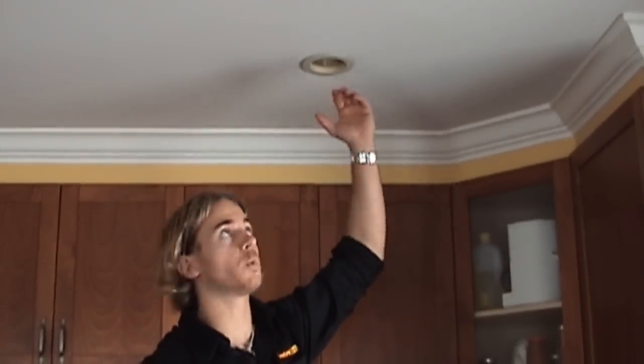There's a lot of air leakage around pot lights. I've checked with the chemical smoke — these ones are sealed up quite well. There's even a bit of caulking around the outside to indicate that they're sealed properly; there's no air leakage.